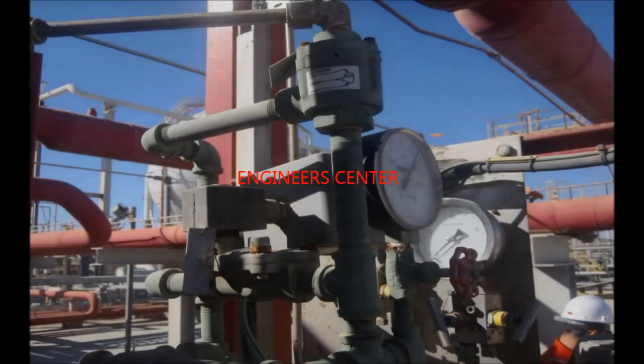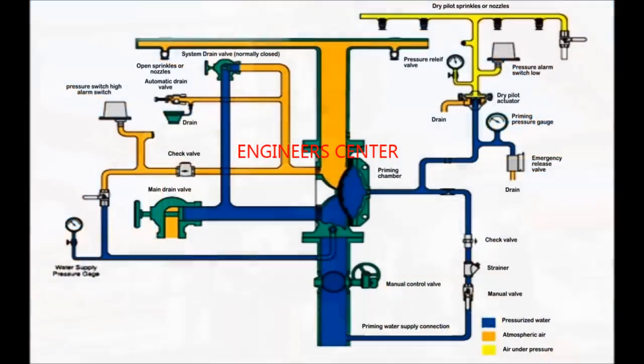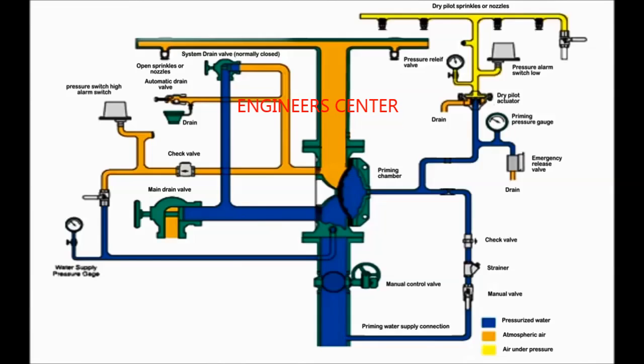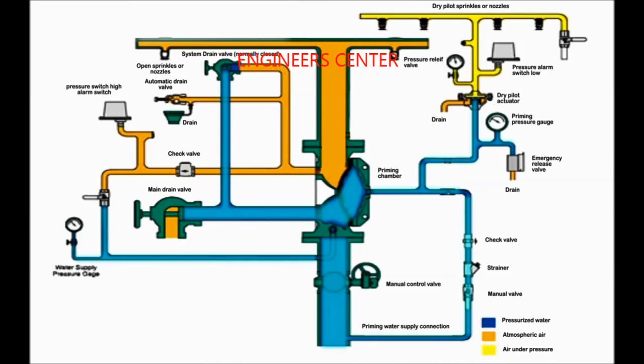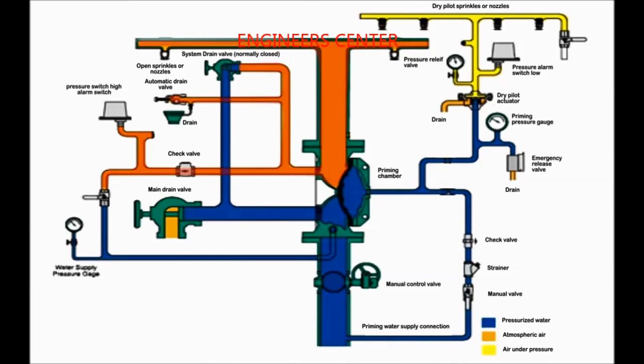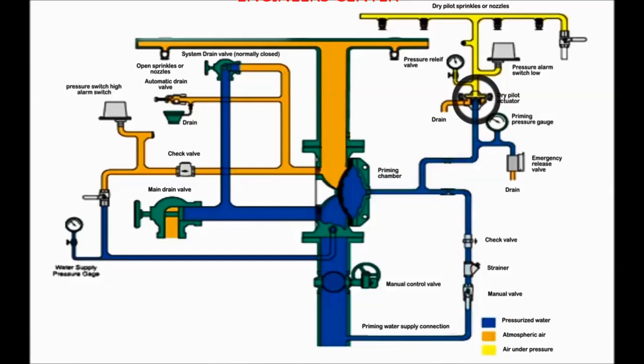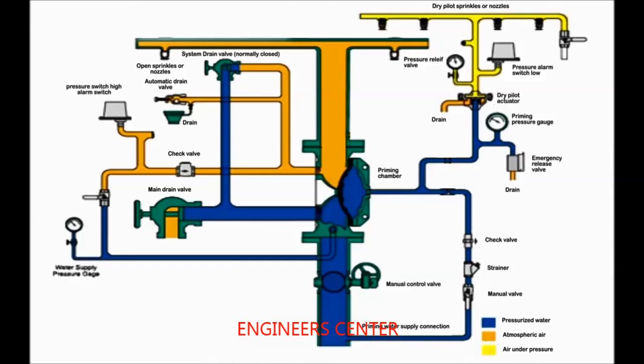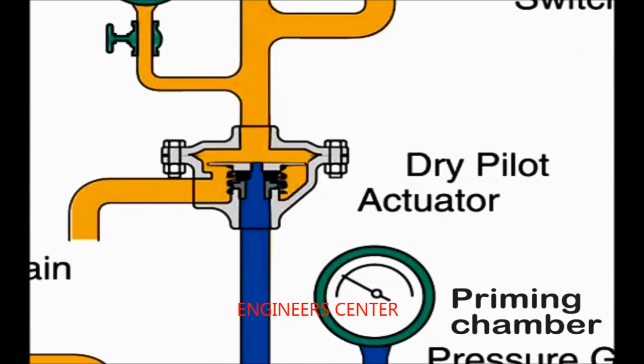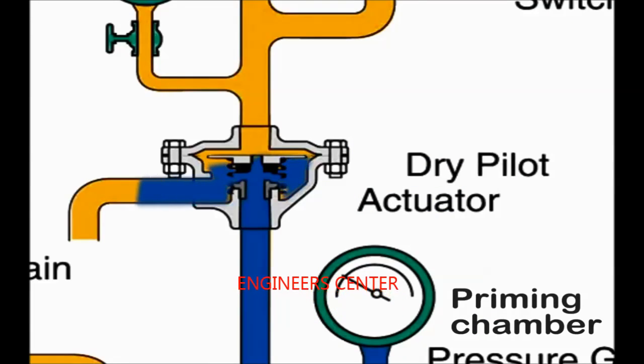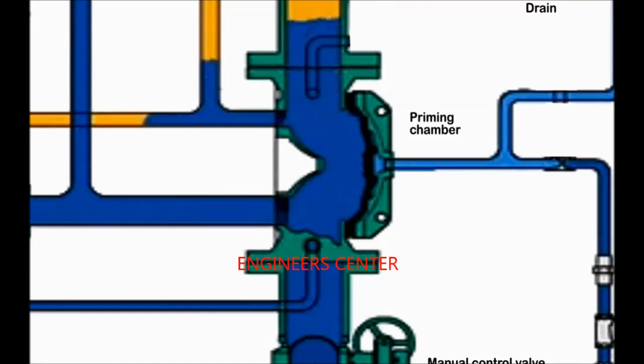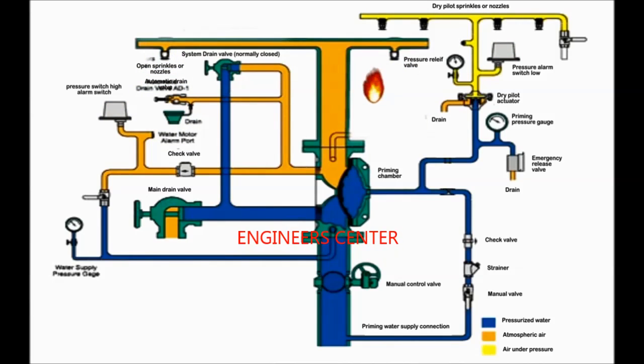Another method of activating the deluge system is the dry pilot actuator. Here is a diagram to explain its operation. The yellow color represents pressurized air between the dry pilot actuator and the sensing element, the blue color represents pressurized water, and the orange color represents atmospheric air. The dry pilot actuator is connected to the priming loop from one side and to the drain from the other side. In case a sensing element detects high temperature, the pressure on top of the dry pilot actuator is released, opening the path to the drain, and therefore the priming pressure is released, activating the deluge system.